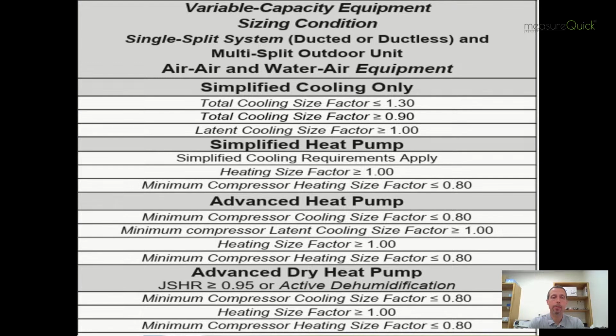And you'll see that when we come to variable capacity systems, it's broken down into two major segments here. You'll notice the first segment up at the top says simplified, right? Simplified cooling only, simplified heat pump. And what we're saying here is that the cooling requirements we talked about still apply. So if we've got a load, say, over 24,000 BTUs per hour of the home, we can oversize by no more than 1.3, or 30%, on the cooling size, but we also want to look at the heating size factor here, and we want to see what that looks like. So now we're going to look at heating and cooling, as well as minimum compressor heating size factor, and see what some of that looks like as well.